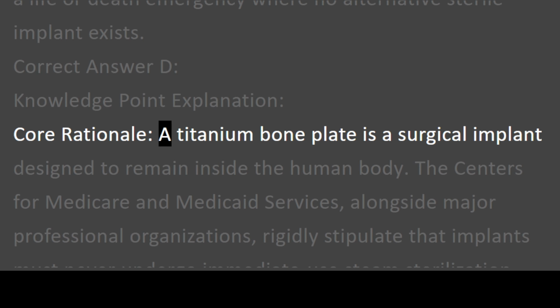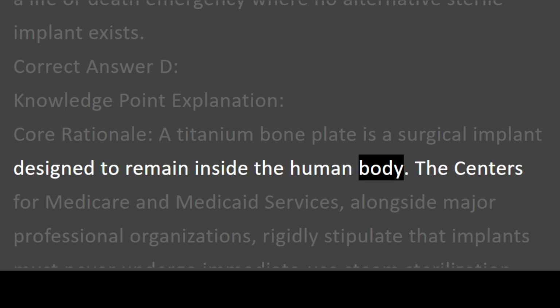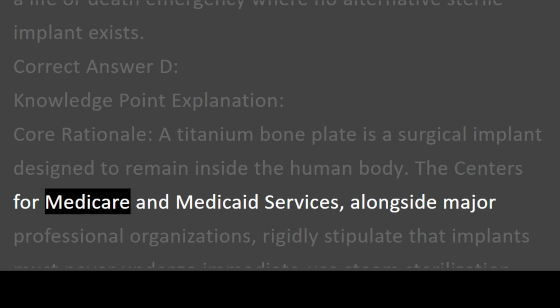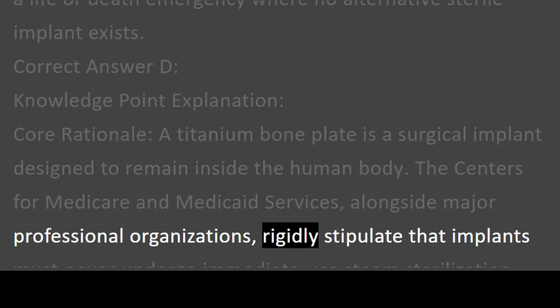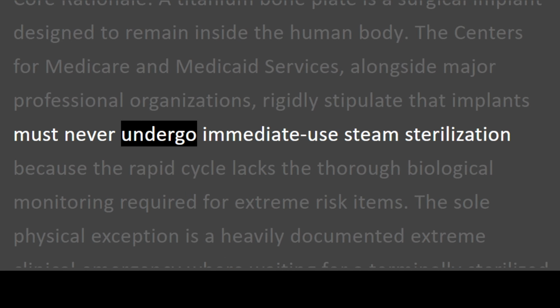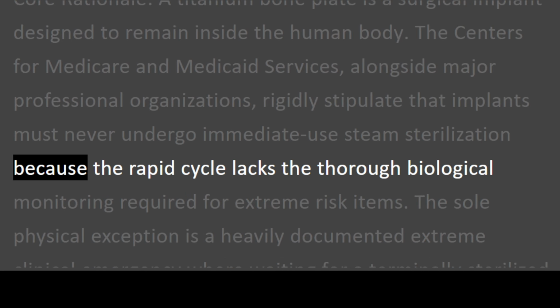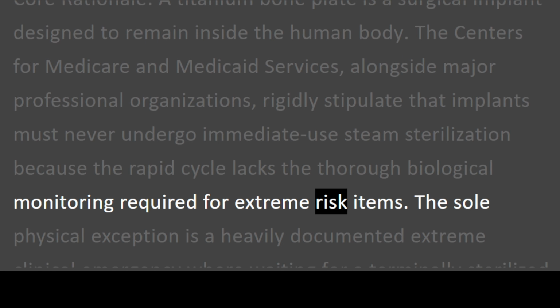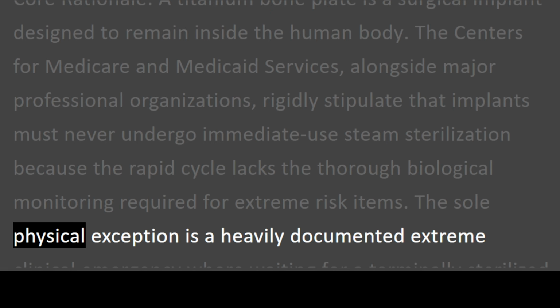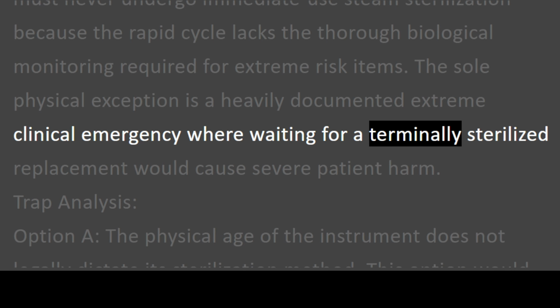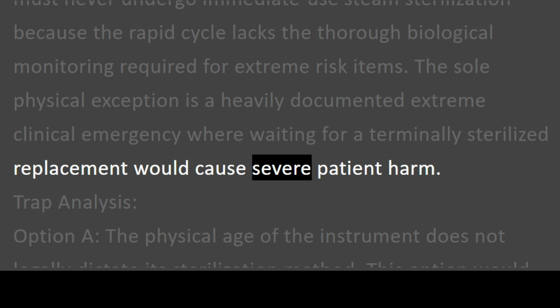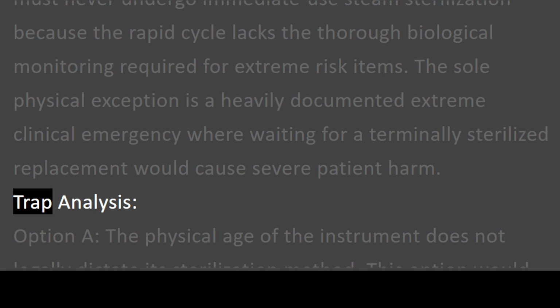Core rationale. A titanium bone plate is a surgical implant designed to remain inside the human body. The Centers for Medicare and Medicaid Services, alongside major professional organizations, rigidly stipulate that implants must never undergo immediate-use steam sterilization because the rapid cycle lacks the thorough biological monitoring required for extreme-risk items. The sole physical exception is a heavily documented extreme clinical emergency where waiting for a terminally sterilized replacement would cause severe patient harm. Trap analysis.